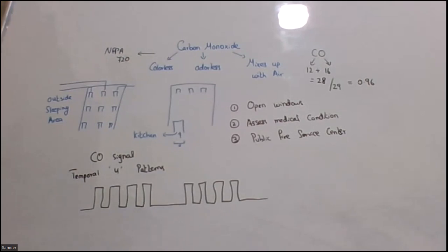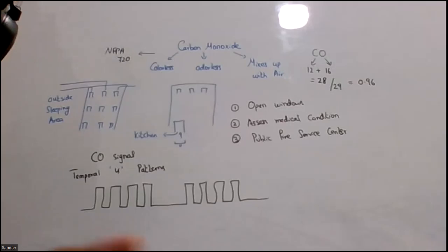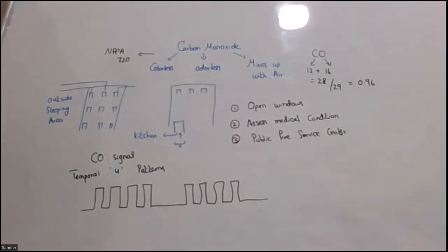Inspection, testing, and maintenance of fire alarm systems. Yes, we will discuss that one. The probability and failure rate is not actually part of the syllabus. But usually in fire alarm systems, operation and maintenance failure, I think we discussed, and I asked this question at the start also, in the ITM, inspection, testing, and maintenance of fire alarm systems. The first device that we usually check in the fire alarm system is the batteries, right? We have discussed this.